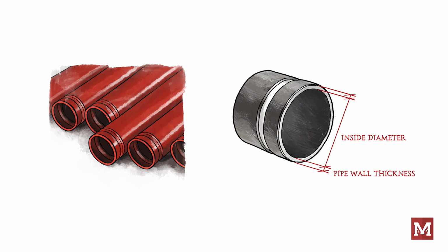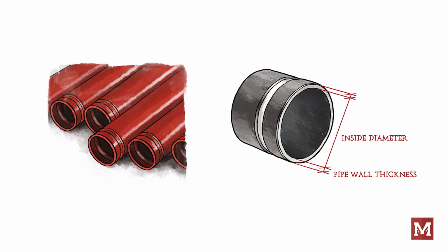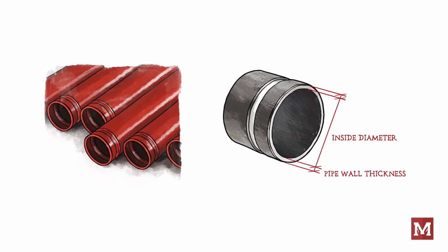The higher the number, the thicker the pipe walls are, and the smaller the inside diameter of our pipe becomes. Pipe with smaller inside diameter will generate a higher friction loss per foot than pipe with a larger inside diameter. Using 1-inch Schedule 40 threaded pipe for pendant drops is very common, even when the rest of the system is Schedule 7 or Schedule 10.